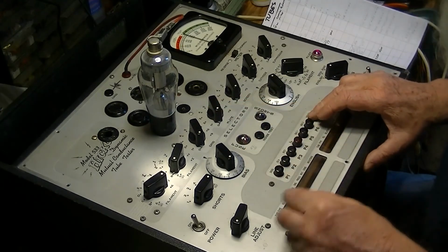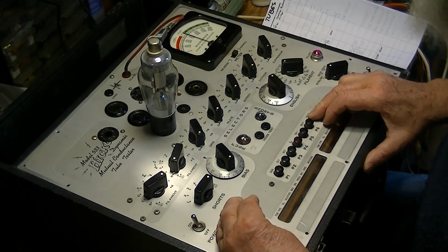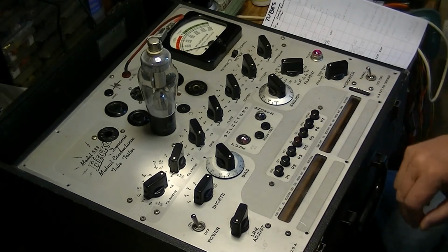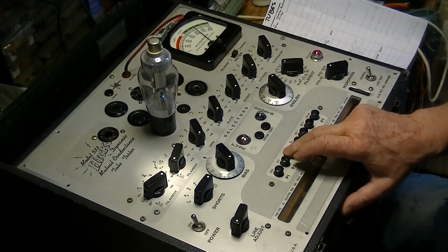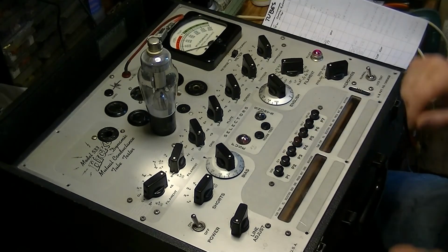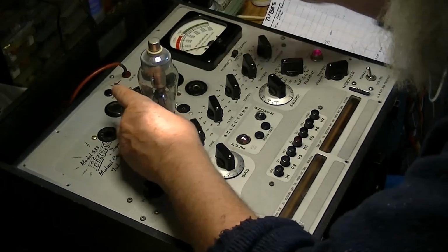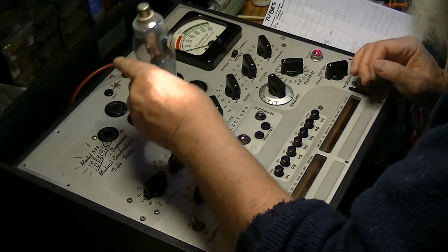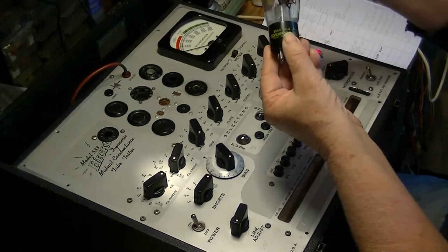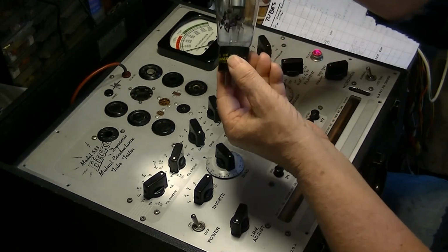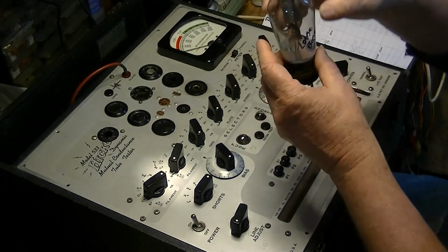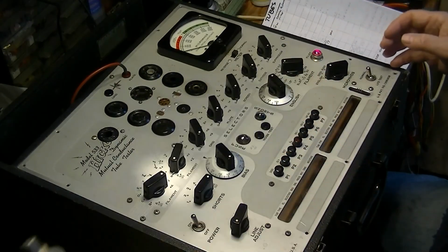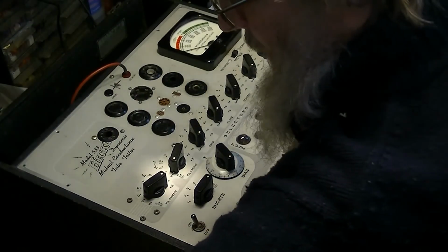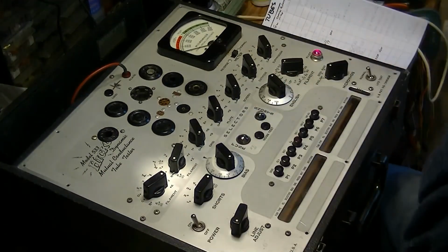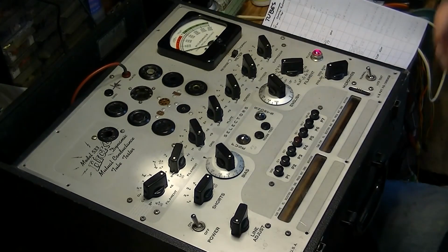This is a fairly heavy filament, and it will require line adjustment. And once the tube is good and warm, you want to double check that. But again, there's nothing but good bad on this, and that's all there is for rectifiers. Both these tubes have a loose base. And so I've written on the tube loose base to remind myself not to grab this tube by the envelope and pull it out of the socket. I probably will try to repair them with some super glue or some kind of a glue, I'm not sure what.